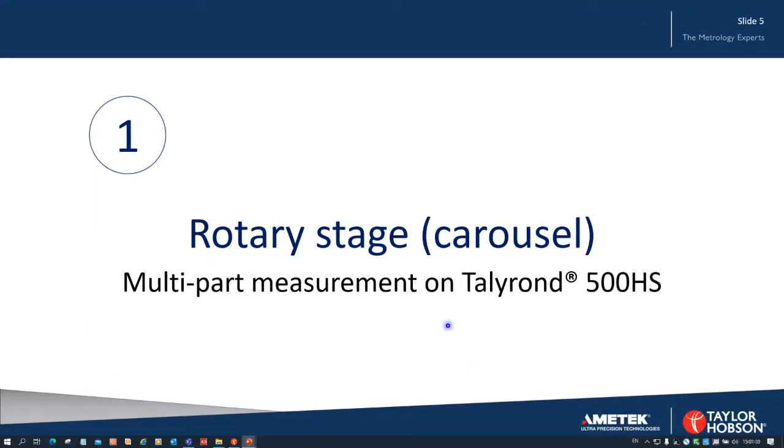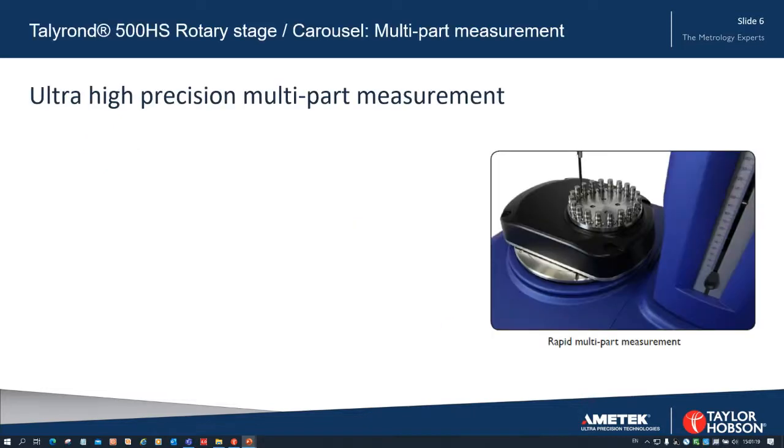So we'll start with the rotary stage, also called the carousel, and this is available on the Talyrond 500HS system. It is in the picture there on the right, and you can see it is loaded with some components. It provides ultra high precision multi-part measurement, and this carousel can be taken on or off.